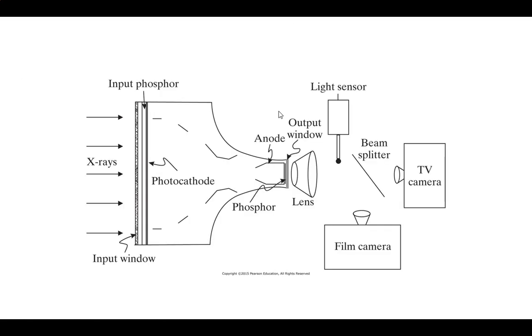All right. I'm going to go real quick on this one. So this is fluoroscopy. It still happens. It's important for some areas. Same basic idea, though. X-rays come in, layer of phosphor. See those little metal lines? Right? This is similar to like a photomultiplier tube. Essentially, you put a voltage differential across this, and when the photons from the phosphor come in, they're going to hit these, cause a cascade of electrons, which will hit the next one, which causes a cascade of electrons, so it multiplies things. Right? Eventually coming down to where this anode is, it's pulling them in, and then it goes to an image.